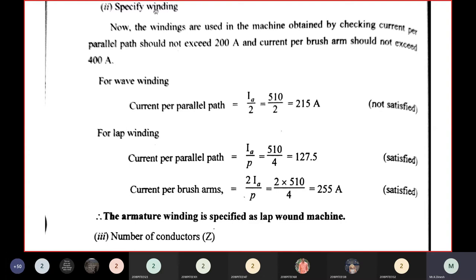To specify winding type in problems, check: current per parallel path must not exceed 200 A and current per brush arm must not exceed 400 A. This determines whether the machine is lap wound or wave wound.